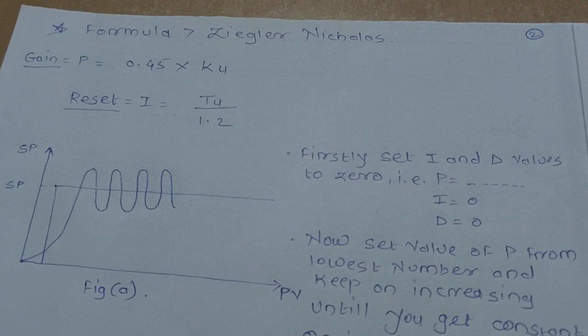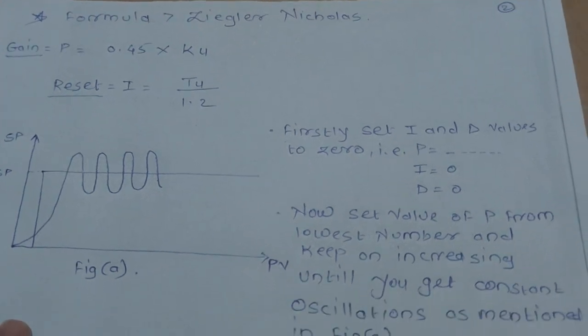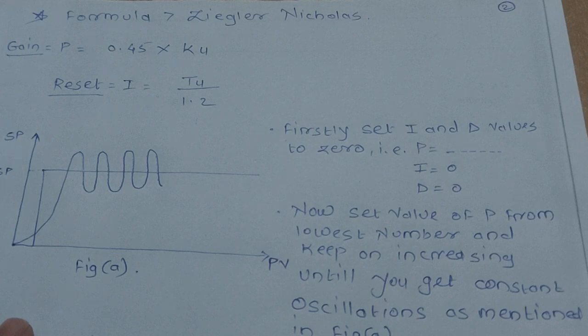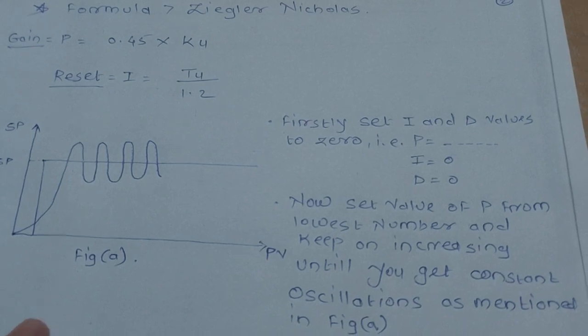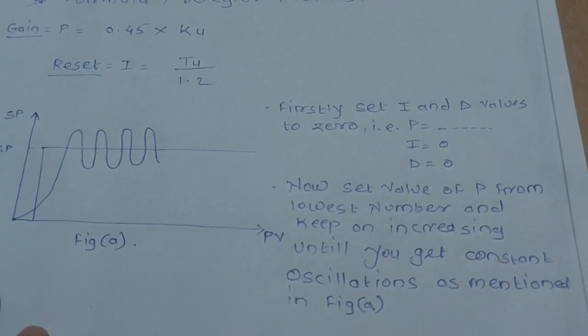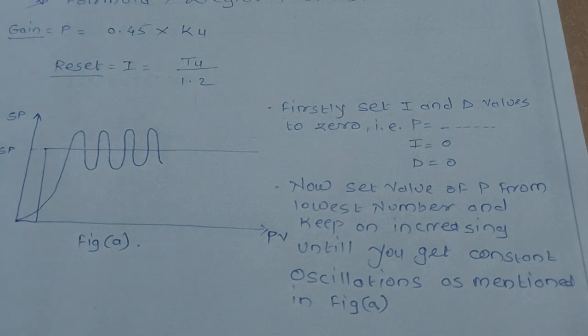To find out the value of Ku and Tu, firstly we have to set the PID controller where I and D parameters will be made zero, and we have to put the value of P from the lowest number and keep on increasing until you get constant oscillations, as mentioned in figure A.